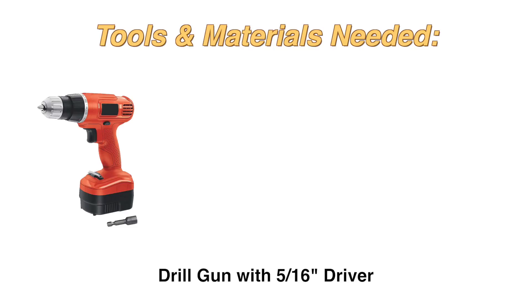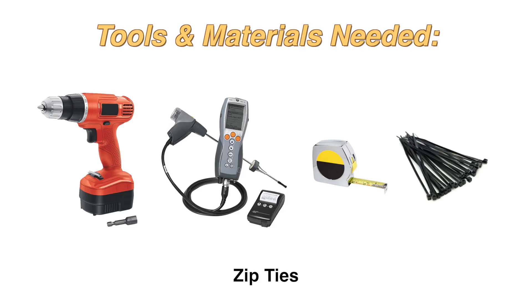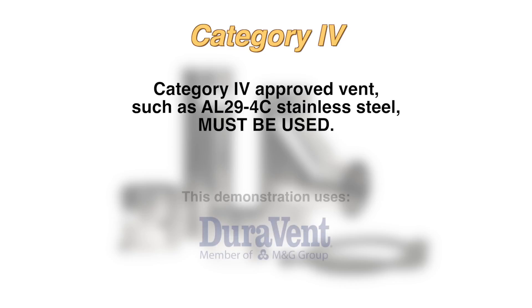The tools and material that you will need are a drill with a 5/16 inch driver, a combustion analyzer, a measuring tape, and zip ties. Category 4 approved vent, such as AL29-4C stainless steel, must be used. We used Duravent in this demonstration.